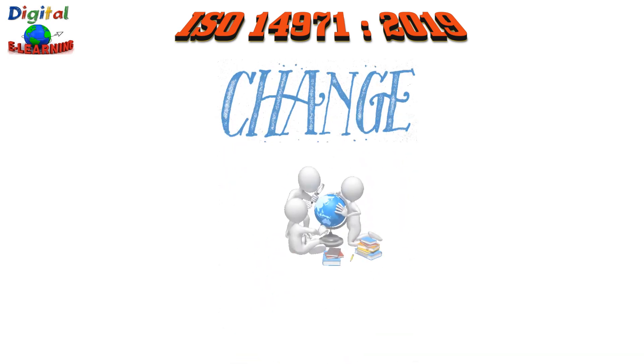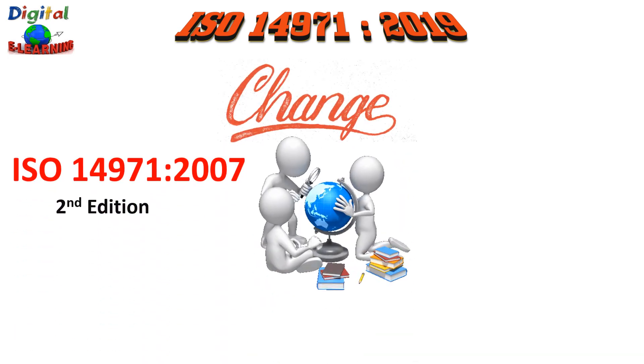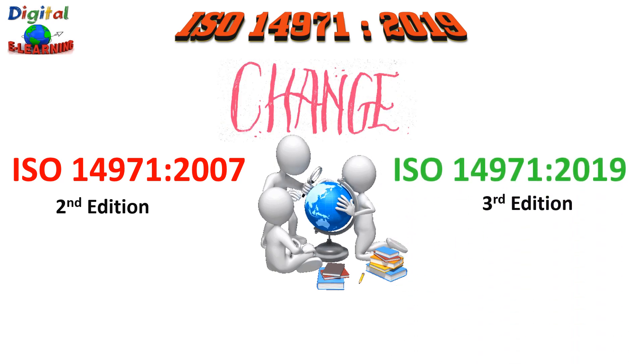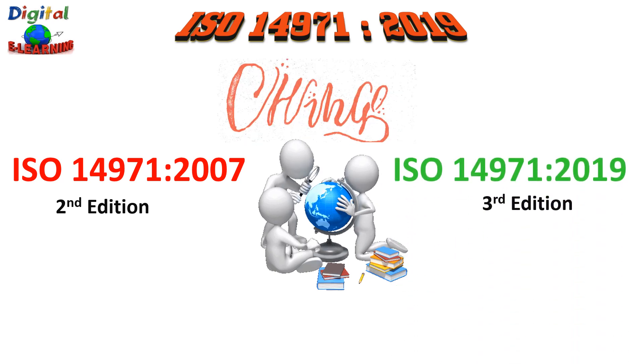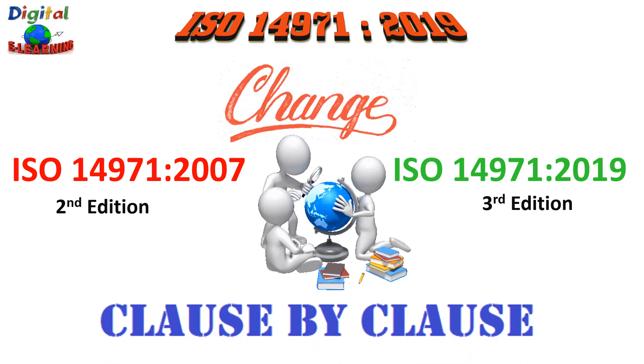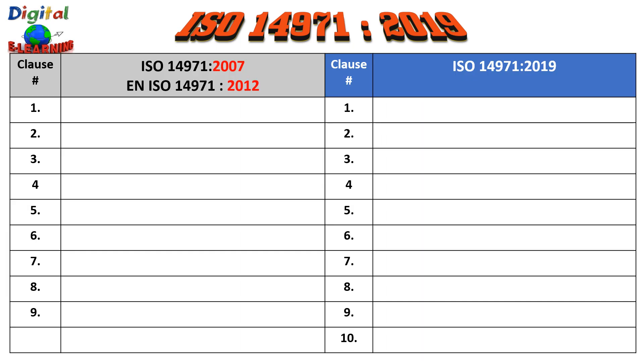We are going to look at what changed between the previous revision — ISO 14971 2007 edition or EN ISO 14971:2012 — and the latest 2019 edition, clause by clause in the coming slides. The first thing that stands out is the new chapter structure in the current revision. The previous revisions were harmonized to MDD but were not harmonized to MDR requirements, so the latest one is built in relation to the new MDR regulation.